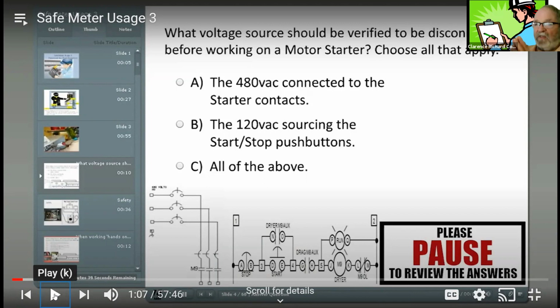So you have to kind of determine that at your plant. Do your motor controls have a little transformer in there to supply the 110 volts for that particular circuit? If you got 10 starters, you're going to have 10 independent transformers. That's how that works. If you're doing it off your circuit breaker panel, you got 10 starters, but you only got one circuit breaker, that's going to turn that off at the lighting panel. So thank you very much.